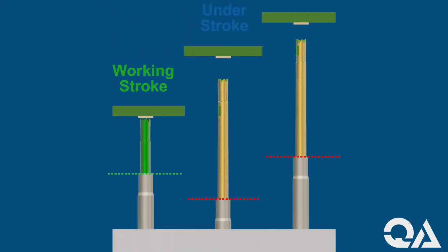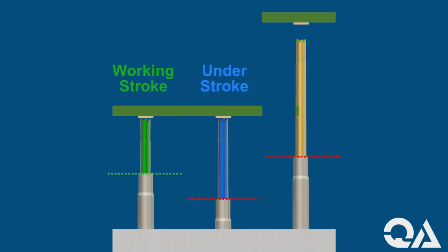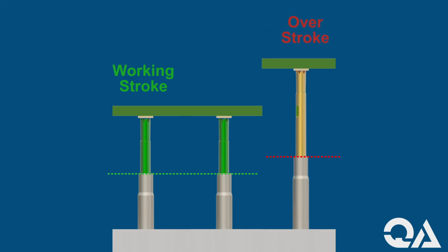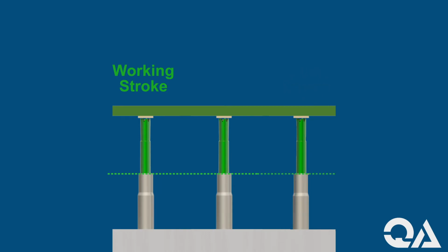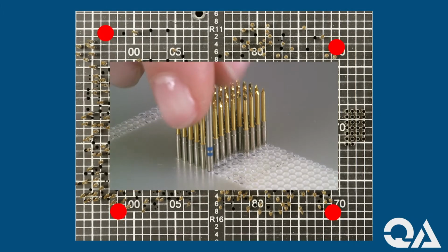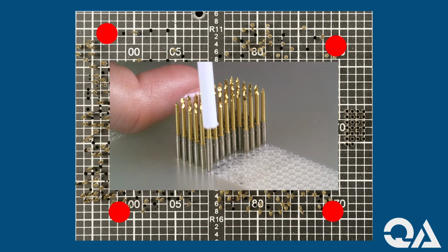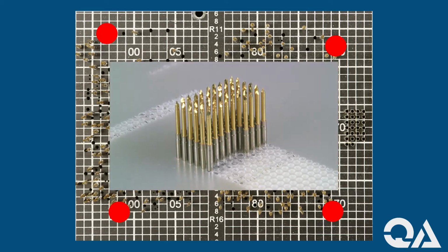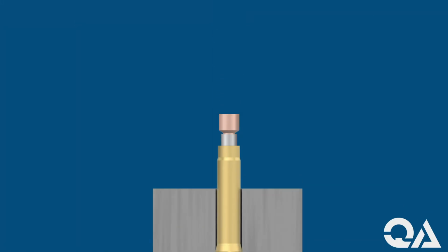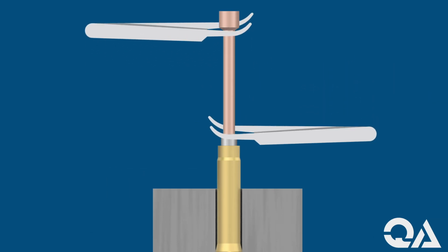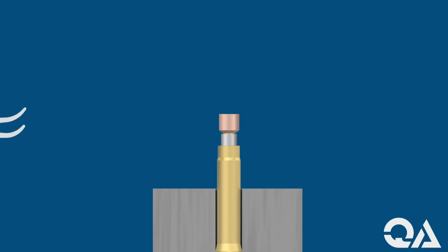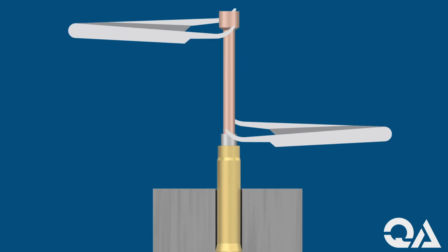If probes are being understroked, sockets or termination pins may need to be replaced at a higher set height to achieve the proper stroke. If probes are being overstroked, sockets or termination pins should be lowered to correct the situation. Finally, remove the indicator probes at each location and replace with the original probes in the fixture. Reassemble the support plate back onto the fixture. Now, you're ready to use the fixture. Please note that an indicator probe will lose its ability to remain in the deflected position after several uses and should be discarded.